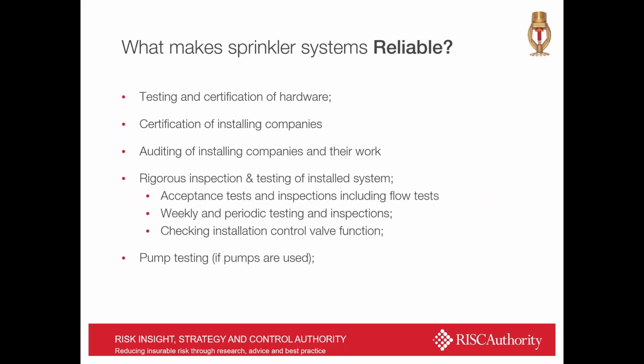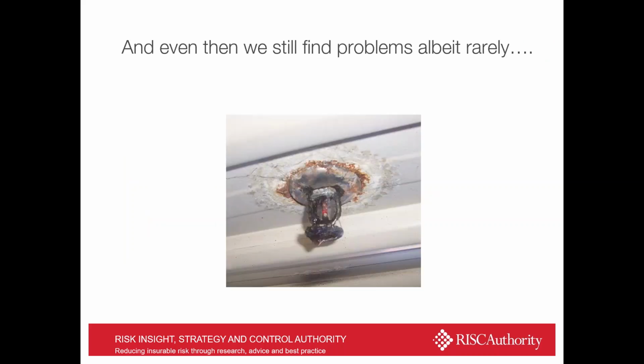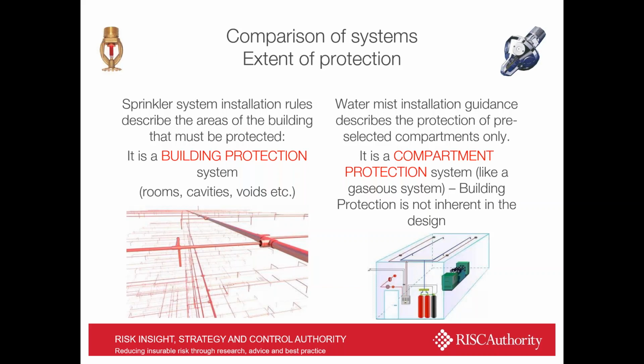There's also testing and certification of hardware, certification of installing companies. There's auditing of the installing companies through things like the LPS 1048 schemes and FIRAS schemes. There's also rigorous inspection and testing of the installed systems by way of acceptance tests, flow tests. There are weekly tests done. Pumps are run up each week as well. And there's checking of installation and control valve function. So as you can see, it's an all-through life solution that has been required to produce reliability within sprinkler systems. But even then, we still find problems, albeit rarely, but it does take a lot to achieve these levels of security. I just want to do a few side-by-side comparisons. Probably one of the primary differences between sprinkler and water mist systems is actually the extent of protection.